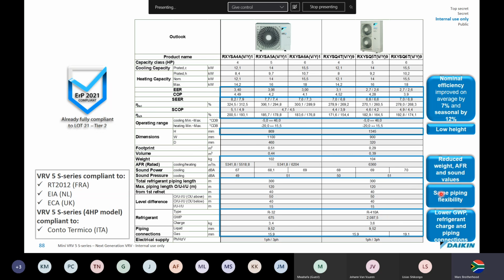You will find, though, that on some systems going forwards, there will be a saving on R32 because R32 has good energy in it. Your suction pipe can be one size smaller. So if you're using a 5/8 pipe, you can maybe use a 1/2 inch. That will be on our current Sky Air and Split Air range. You'll see the pipes are smaller. It's because you use less charge and the refrigerant has more energy in it. It's like petrol has a lot more energy when you burn it than diesel. And another advantage, as we said here, is lower global warming potential, lower refrigerant charge, and the piping connections.